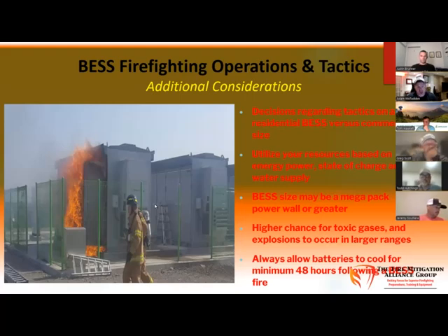Now hear me out on this. We already talked about the lack of ventilation, the stranded energy, the heat, and the risks involved with these batteries. Is it a few cells at a time? Is it only a couple that are propagated? Or is it multiple banks inside one of these energy storage systems putting us at risk? We don't know. So while you confirm the fire is out, using thermal imaging cameras, heat guns, air monitors, PIDs for volatile organic compounds which do come off these batteries, and many other devices available to us, the ventilation issue and that risk is still prevalent over a longer period of time that we need to be aware of.